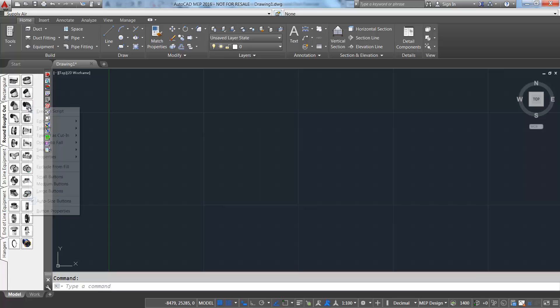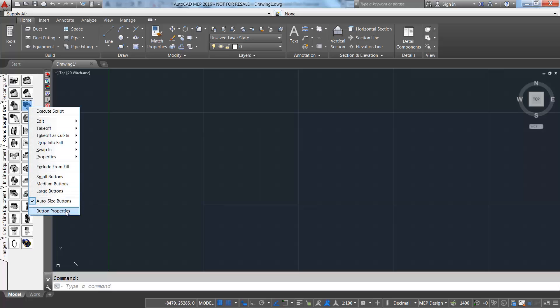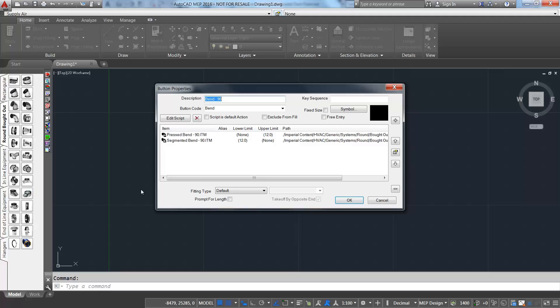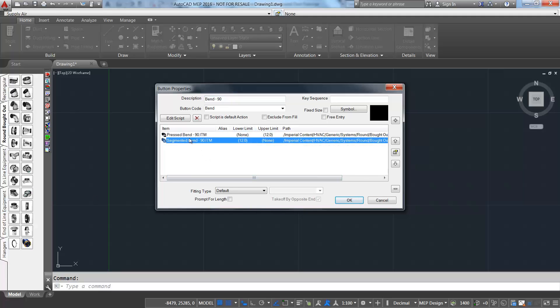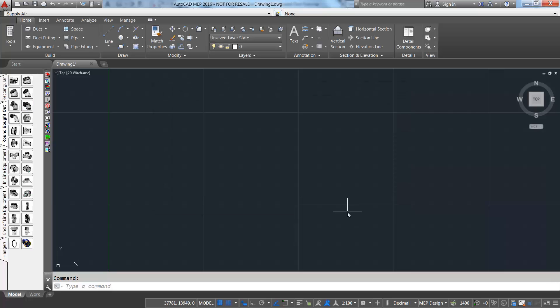When we look at the button properties in CADmep, we can see that 90 degree elbows less than 12 inches use a pressed bend, and elbows 12 inches or greater use a segmented bend.